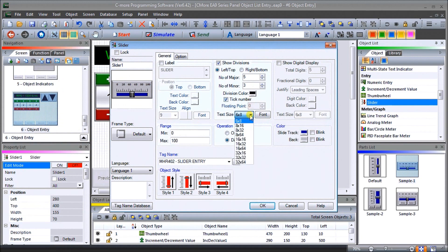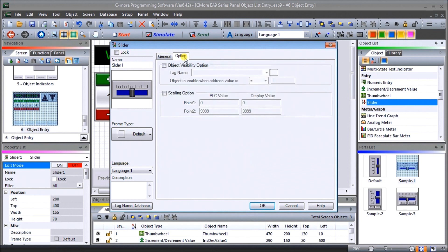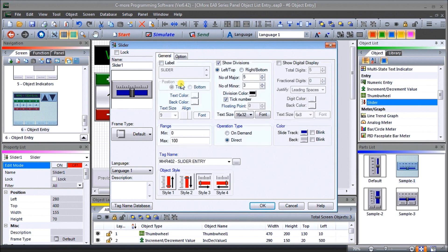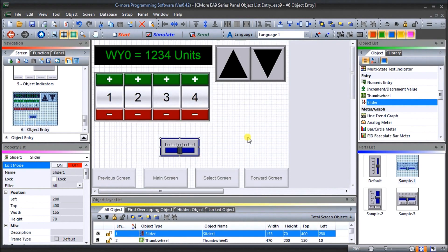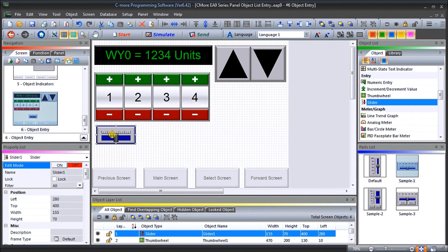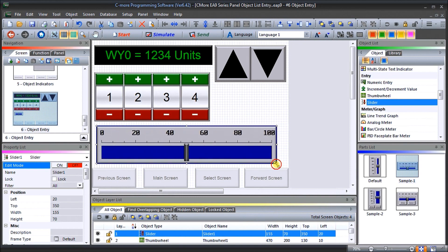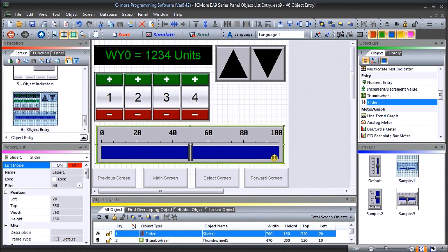We'll set text size to 32, which should be large enough. Under option we have object visibility which we won't set, and then scaling. Under scaling, our PLC value goes from 0 to 4095 and our display value is 0 to 100 — so that zero to 100 on the slider represents 0 to 4095 in the PLC. Hit OK, position the slider across the full length of the screen, and hit save.